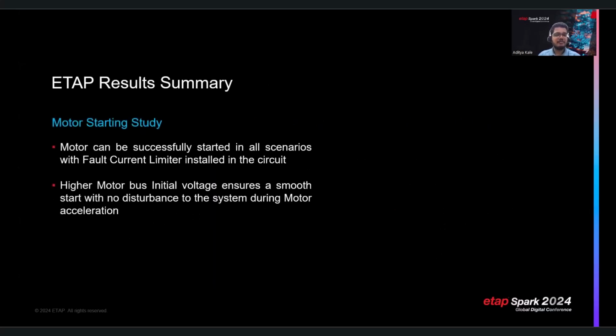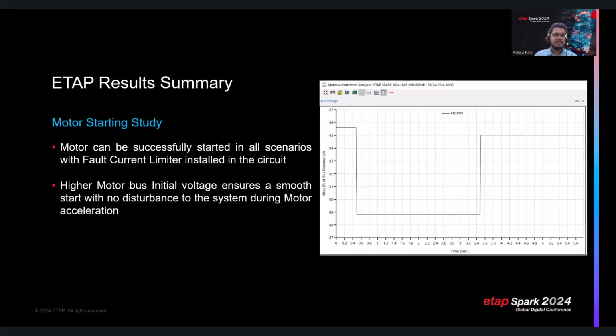Let's also look at a brief snapshot of the motor starting study that we did. What this shows is the voltage drop during acceleration. In the single-ended scenario with the FCL in circuit, we see the initial voltage is slightly above 95%. And at 0.5 seconds, we start the motor, where we have a voltage drop during motor acceleration. This takes the motor bus voltage down to around 88 to 89% of the voltage. This is the drop during the motor starting. This voltage drop does not affect any other associated loads. There are no other risks to the motor starting. So we can conclude that with adding the FCL, having no reactors in circuit, we are able to start the motor successfully.